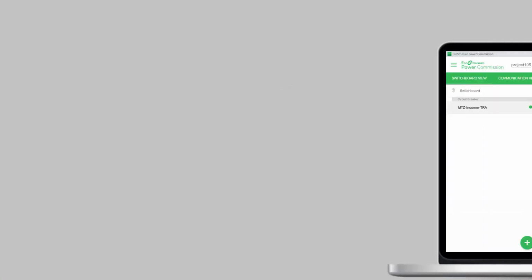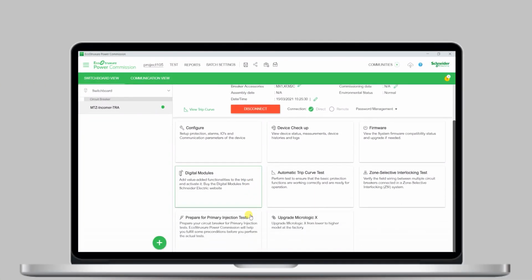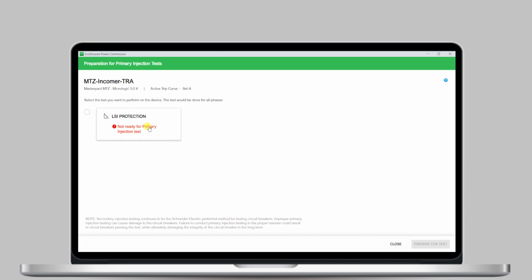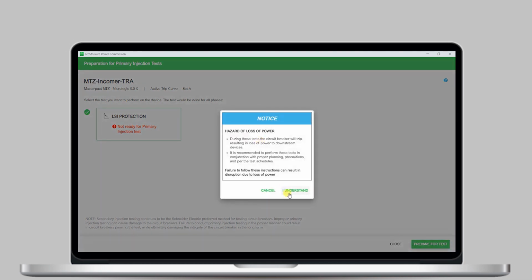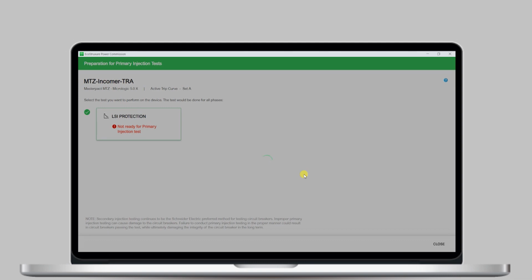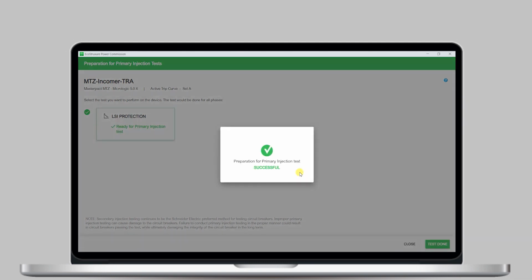Wow, that's pretty handy. Now I'm going to go ahead to the last test function, which is not required all the time, but just in case your customer wants you to perform a primary injection test on the circuit breakers. You can use this feature to prepare for such test. Turn off the thermal memory and ground fault protection, and then use an external power source to generate the fault current. Remember, as much as possible, we recommend to use the automatic trip curve test to prolong the life of the breaker.